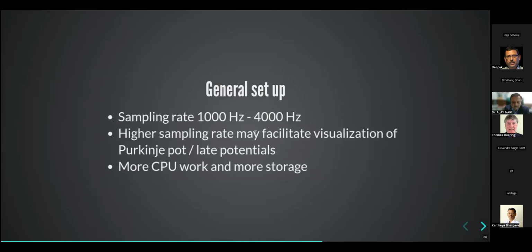Sampling rates are usually 1000 to 4000 hertz, like I said. In most EP systems, a 1000 hertz sampling rate is sufficient, but you can go up to 2000 or 4000 hertz, if your system allows that, when you want to see very sharp potentials like late potentials or Purkinje potentials. The more samples you take, of course, the more samples are being written to storage and handled by the amplifier, so it becomes more load on the system and more storage space is taken up.